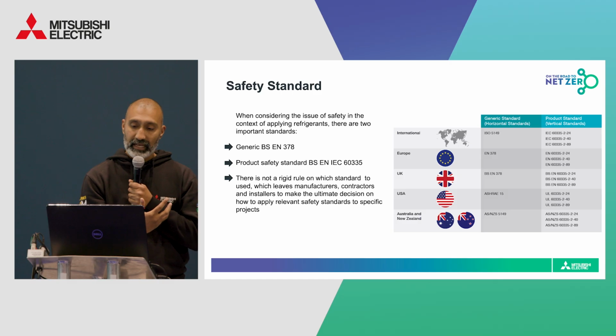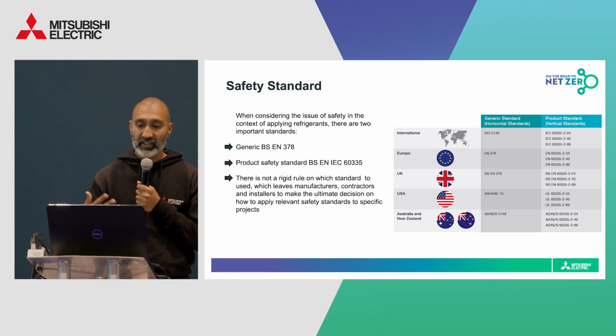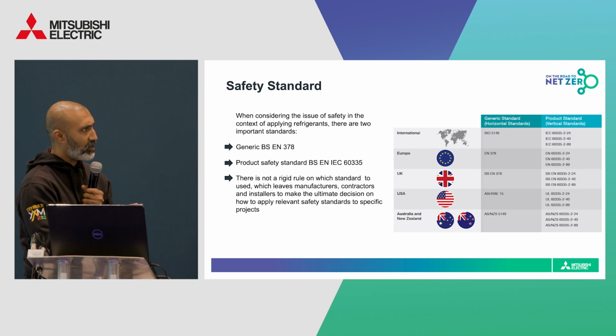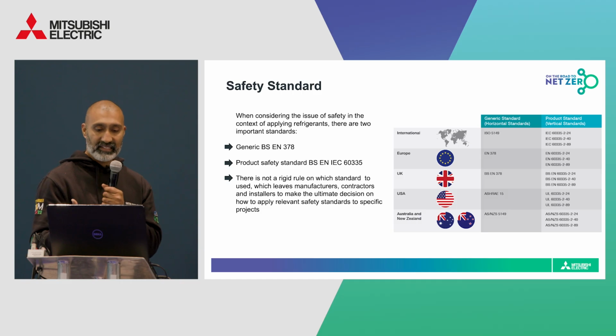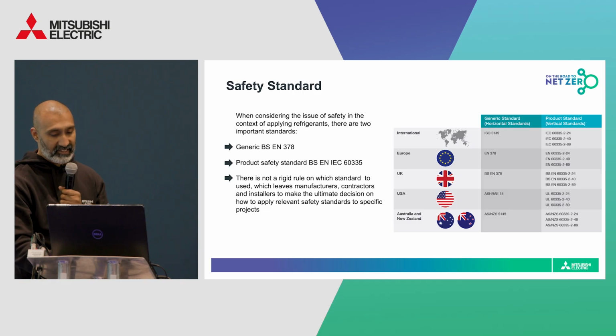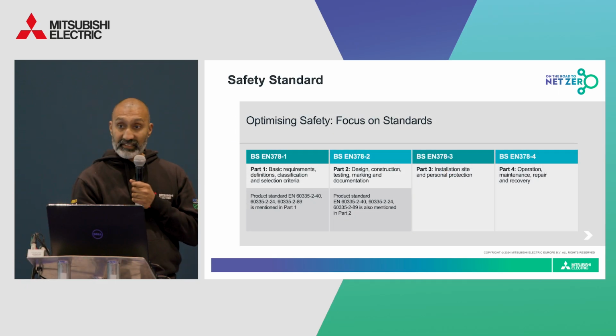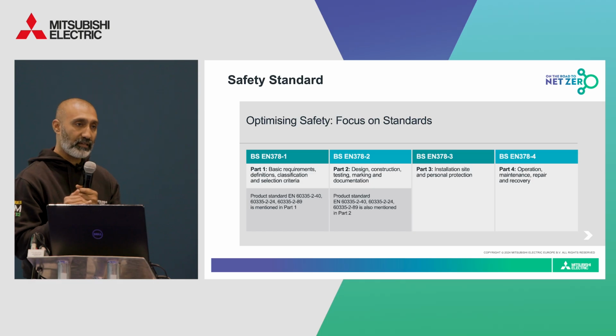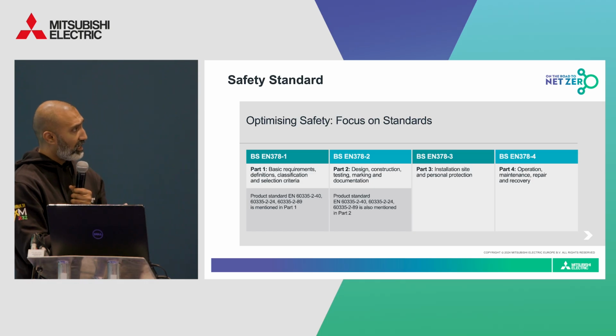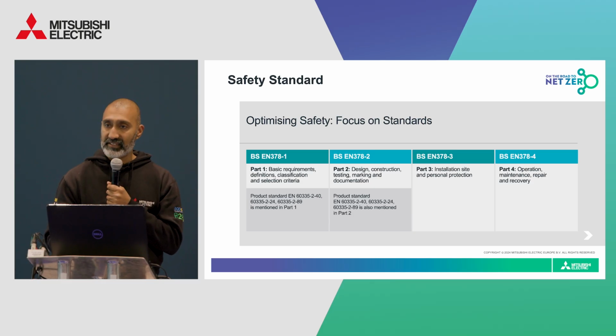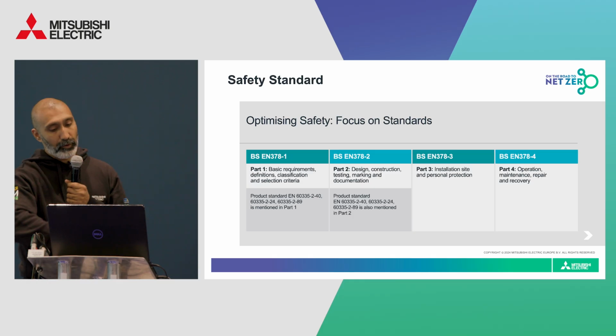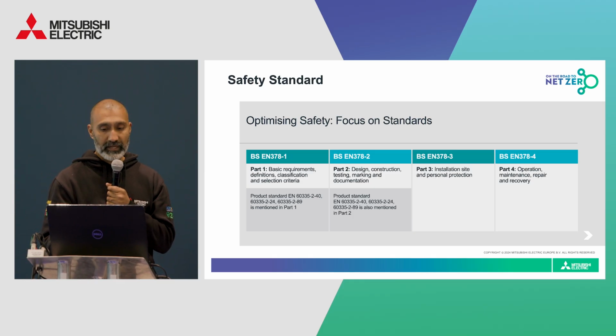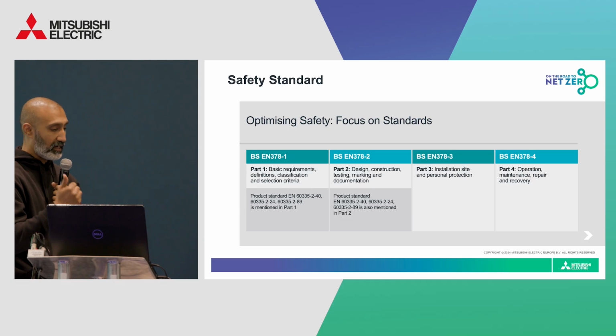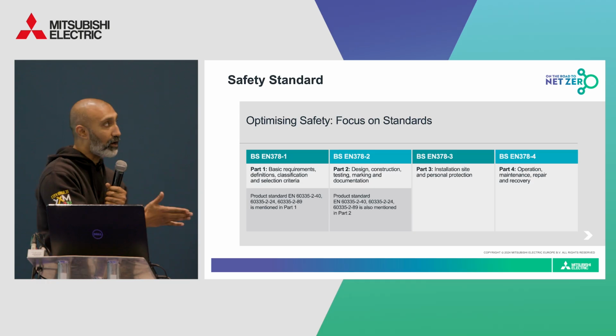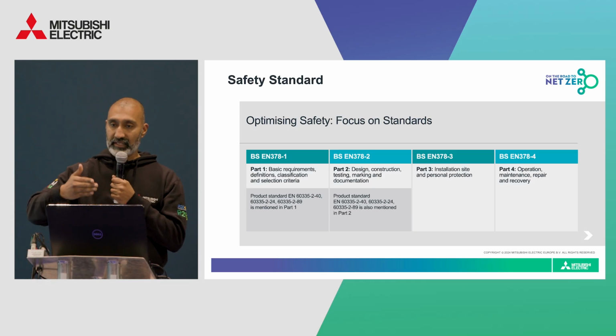Now, standards can be horizontal, providing broad guidelines, or vertical, which are specific to certain products or industries. And these standards are essential for promoting safety and best practice in the sector, ensuring reliability and consistency. When considering safety risks for HVAC installations, it's really useful to consider BS EN 378, and the standard is split into four separate parts, each providing guidance on how to achieve a safe system. So EN 378 addresses safety throughout the entire life cycle of the refrigerant using system, from design and installation through to commissioning and maintenance. And it involves various building engineering professionals, consultants, installers, commissioning engineers, and each part of the standard is directed towards different people or different personnel.